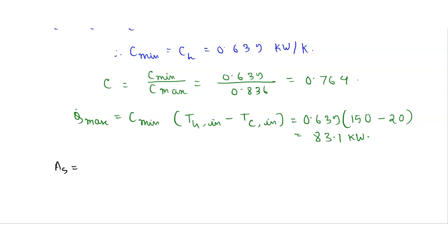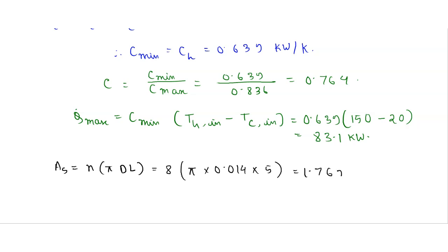The heat transfer surface area A_s equals n times pi times d times l, where n is the number of tubes, d is the diameter of the tube, and l is the length. Here n is 8, multiplied by pi, multiplied by diameter 0.014 meter, multiplied by length 5 meter. After solving this we get heat transfer surface area of 1.76 meter squared.